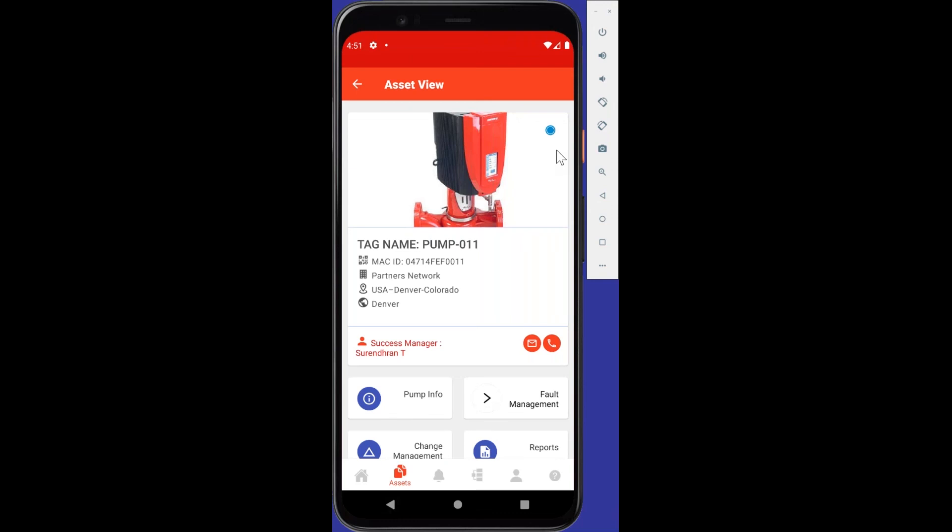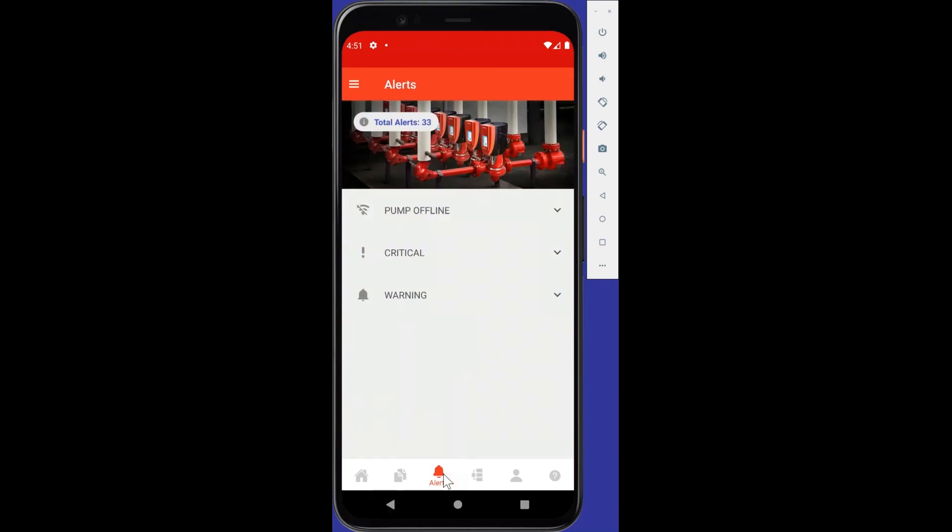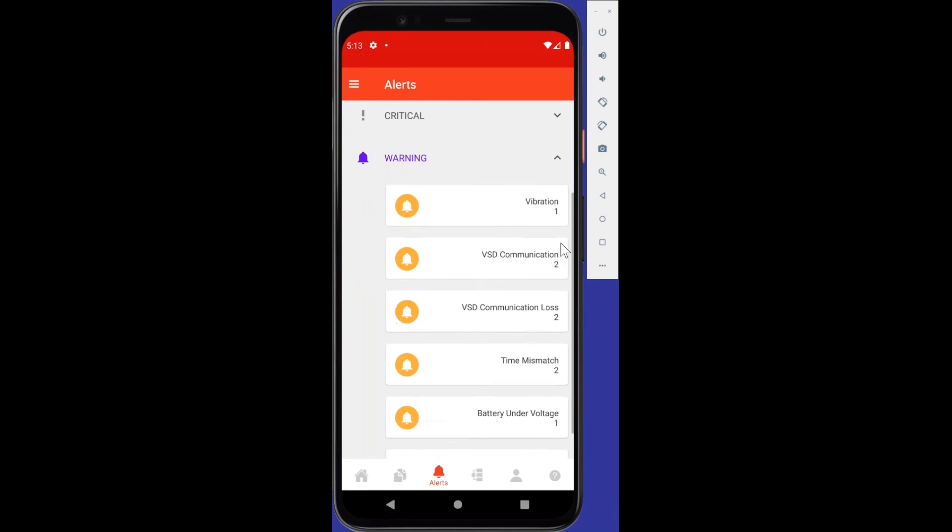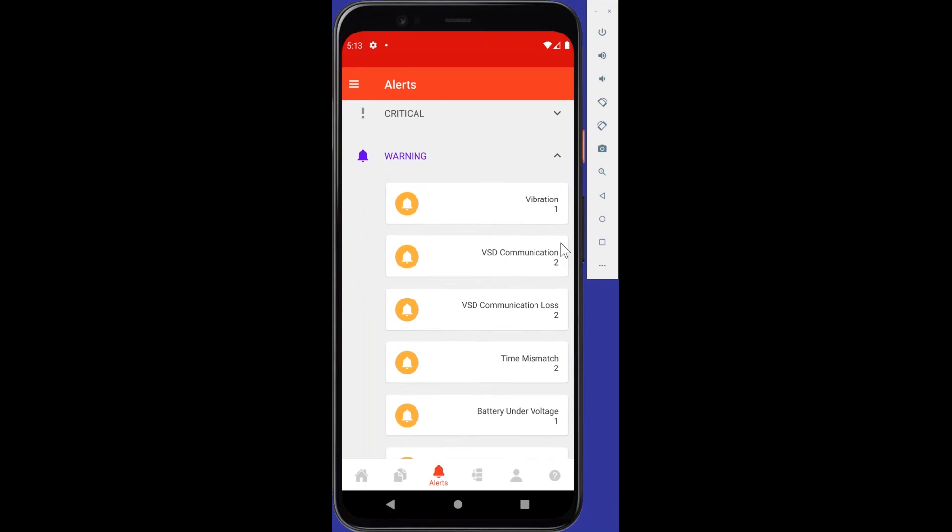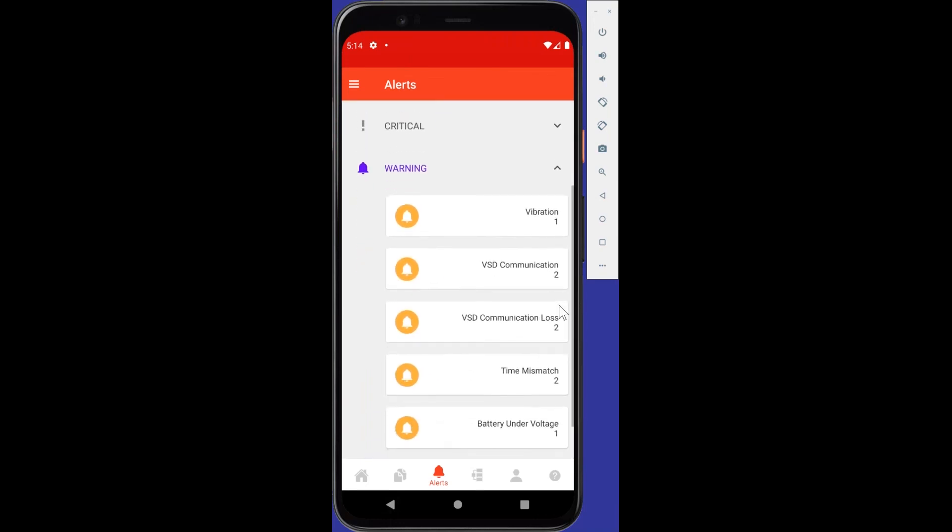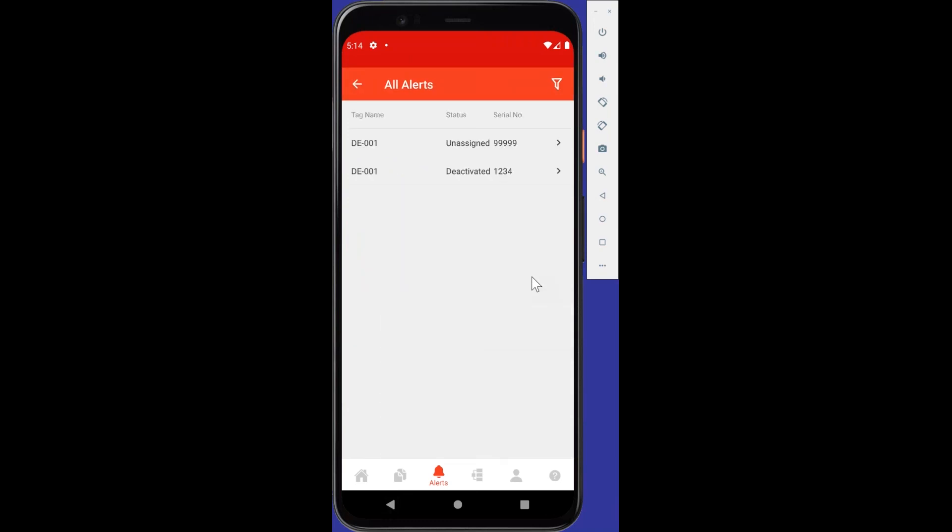Now, if I go ahead and click the next icon here, the bell notification or alert, here all the active, critical, and warning alerts across the entire account are listed, much like the assets are all listed. And by selecting one of the instances of an alert type, whether it's critical or warning, it will take you to the pump asset management view where you can view all of the active alerts in further detail. So first one we have listed there are pumps offline. In this simulated environment, it's showing 23 are currently offline. We also have the critical. There's one pump with an excessive vibration alert. And then there's the warnings where we have vibration, VSD communication, VSD communication loss, time mismatch, battery under voltage, and hand mode timeout. So if I go ahead and click, let's see, VSD communication, it's going to show me two pumps that currently have this issue. If I click the first guy, let's see what it brings up.